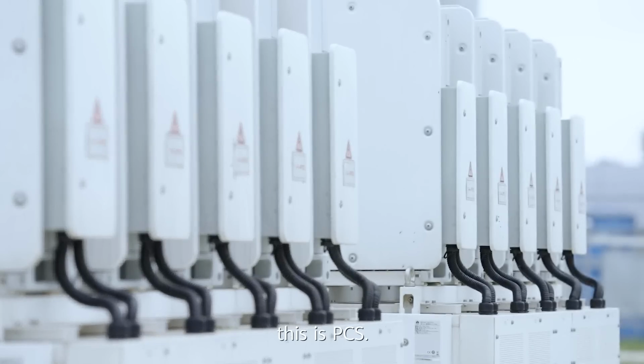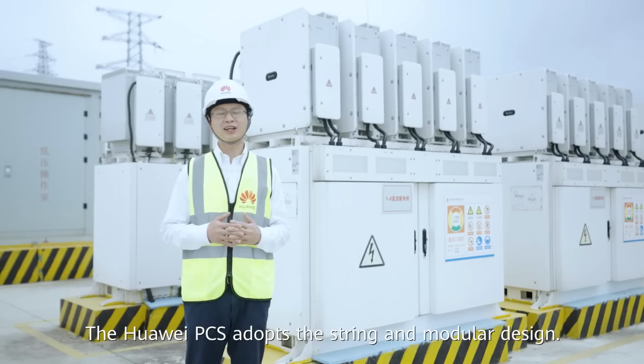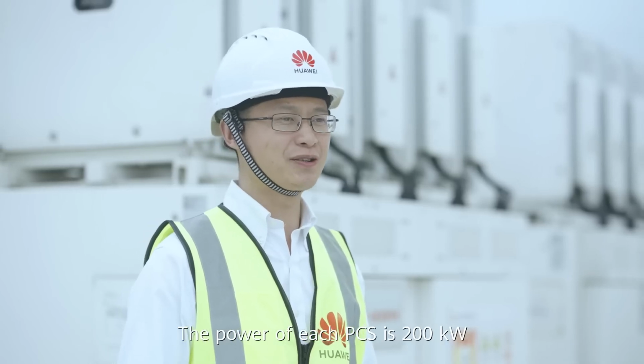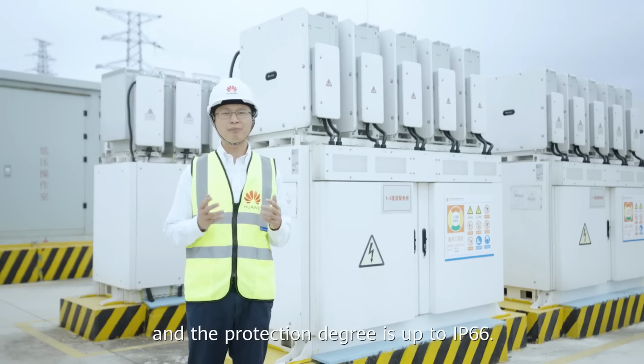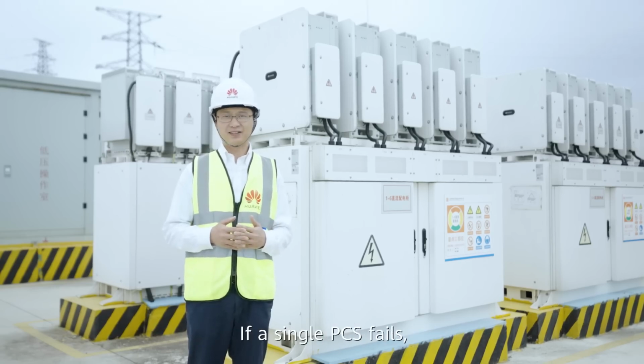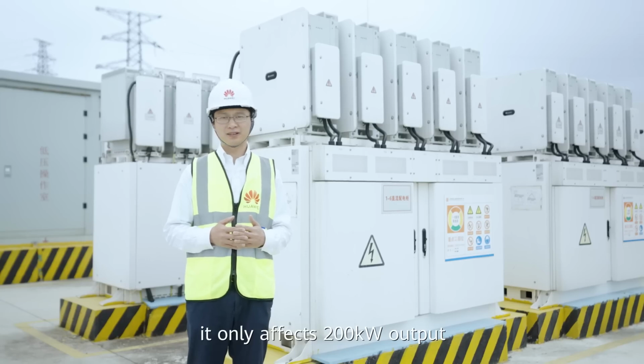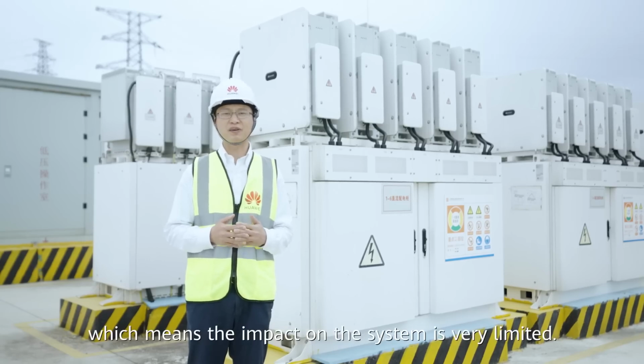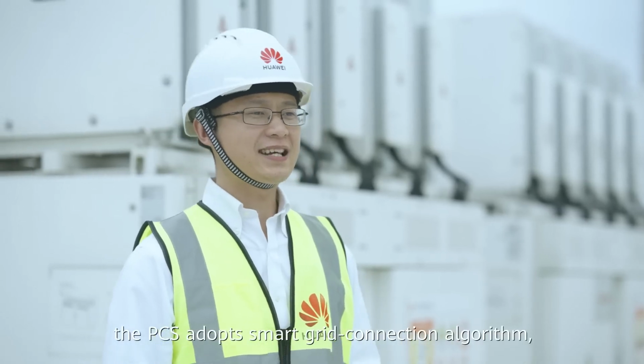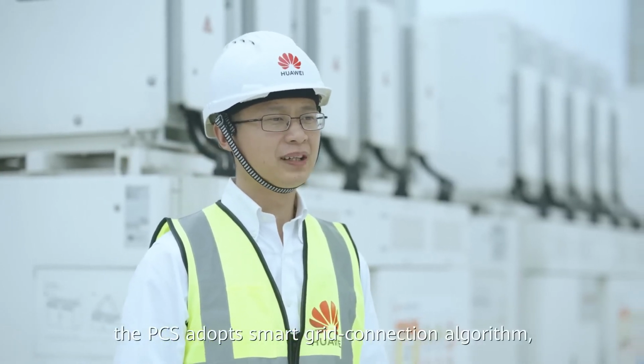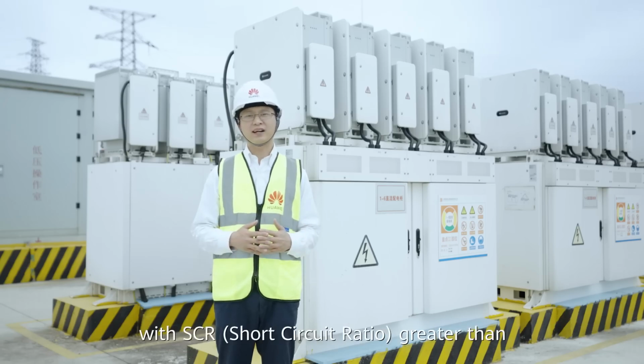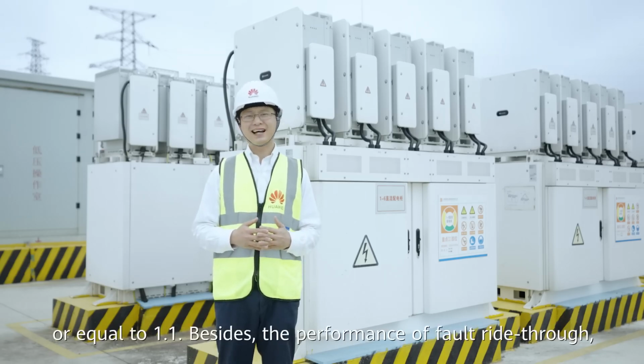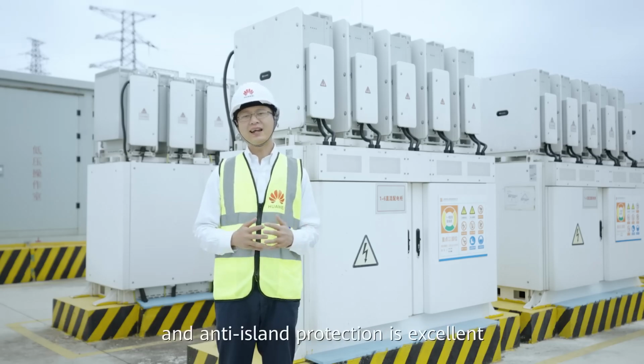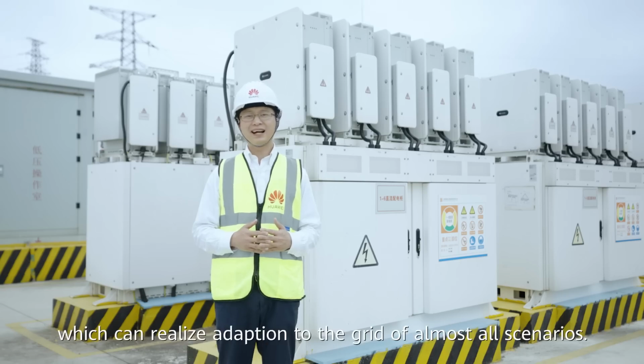This is PCS. The HUAWEI PCS adopts a string and modular design. The power of each PCS is 200 kilowatts, and the protection degree is up to IP66. If a single PCS fails, it only affects 200 kilowatts output, which means the impact on the system is very limited. Meanwhile, the PCS adopts smart grid-connection algorithm, and can realize stable grid connection with SCR greater than or equal to 1.1. Besides, the performance of fault ride-through, high and low voltage ride-through, and anti-islanding protection is excellent, which can realize adaptation to the grid of almost all scenarios.